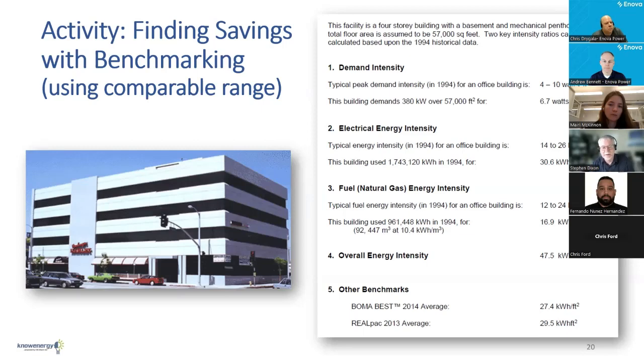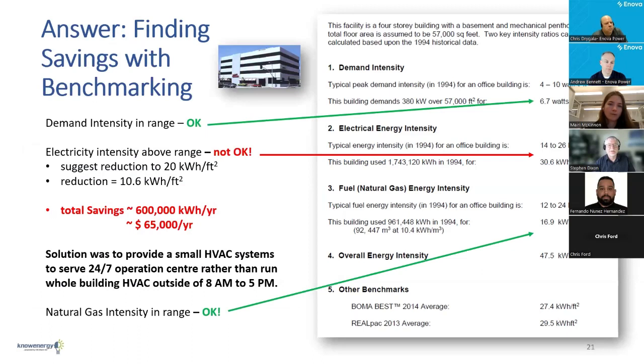Now, I could look at the overall intensity and say that's way above other buildings, which it is. But what I actually did was ask how those three intensities compare to one another. Very quickly I determined that even though the demand and the gas energy intensity were kind of in the typical range — 6.7 for demand with a range of 4 to 10, 16.9 for gas with a range of 12 to 24 — the electricity was 30.6, way above the range.